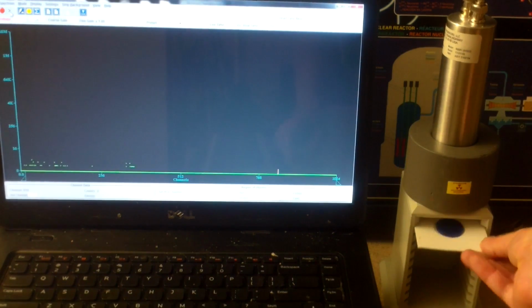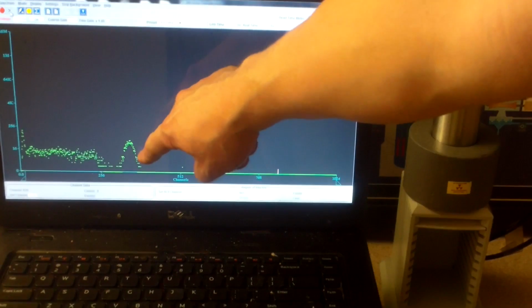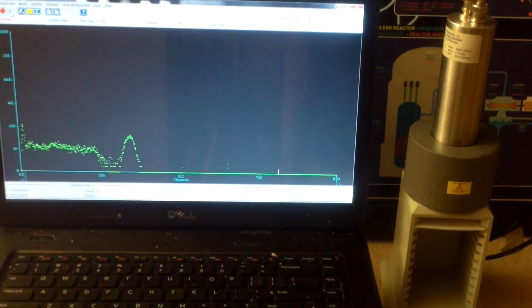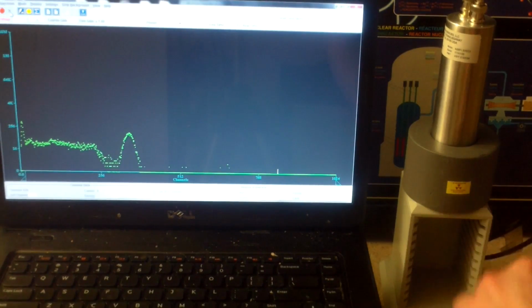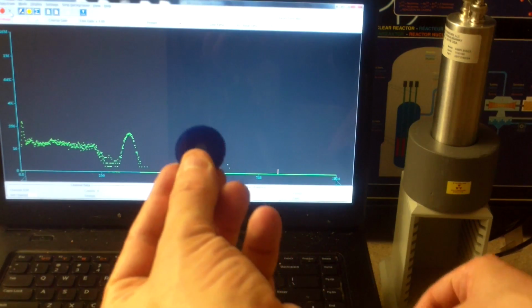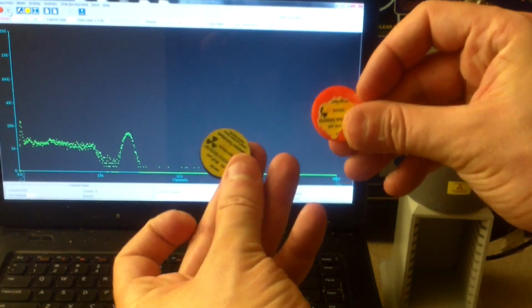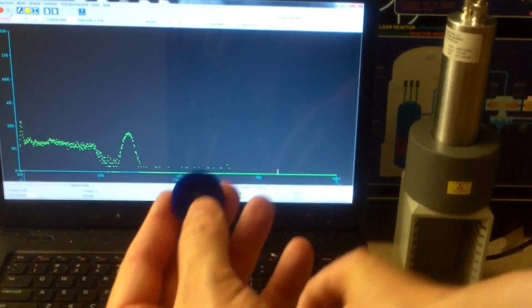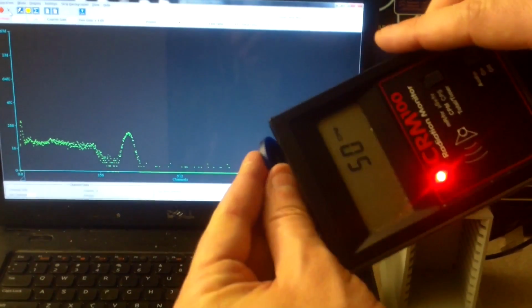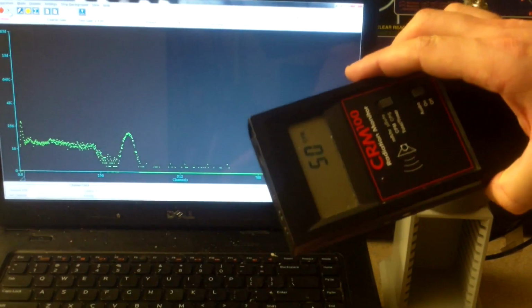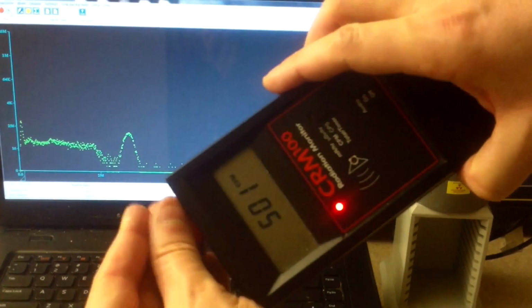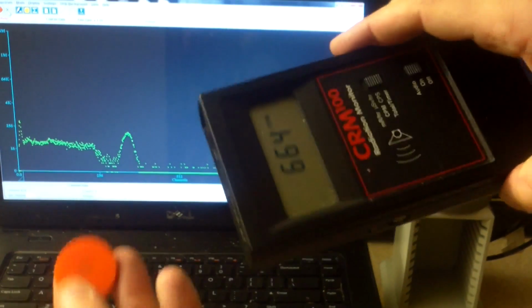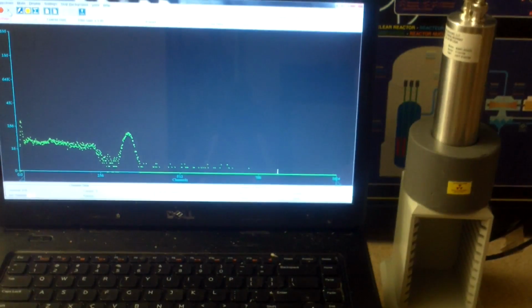Let's get rid of that, put the second one in. What do we get? We get a peak right here at 662 keV, classic cesium-137. So this is cesium-137, this is cobalt-60, and they say so on the little chips. But the problem, of course, with the Geiger counter is it does exactly the same thing with both of them, except this one's a little bit weaker, so it does a little bit less. But otherwise, it's doing the same thing. It's just making little ticks.